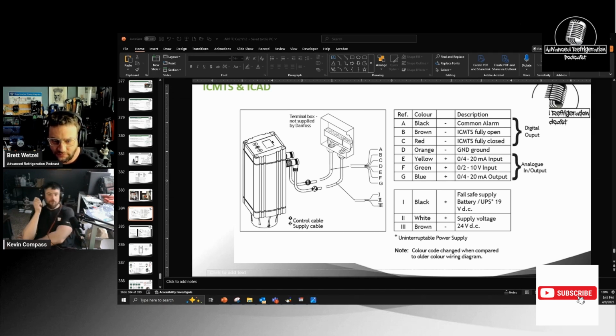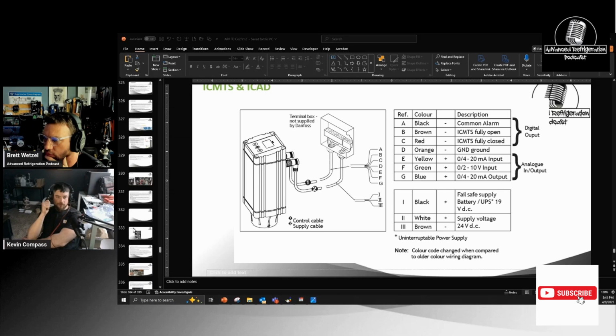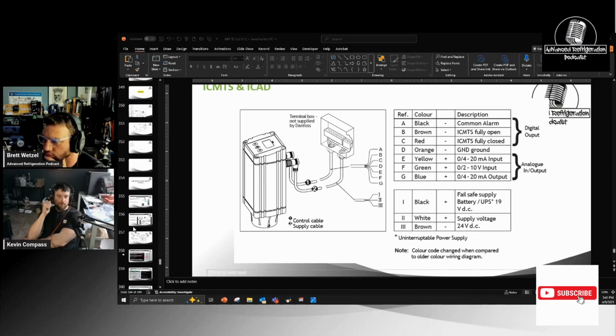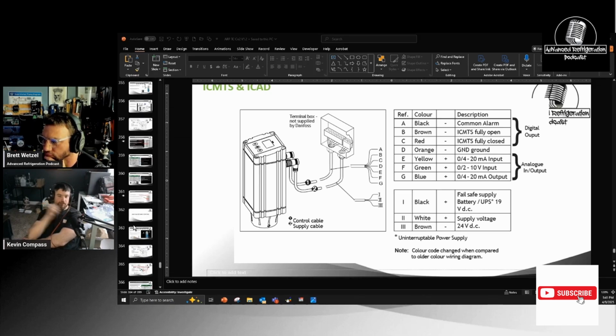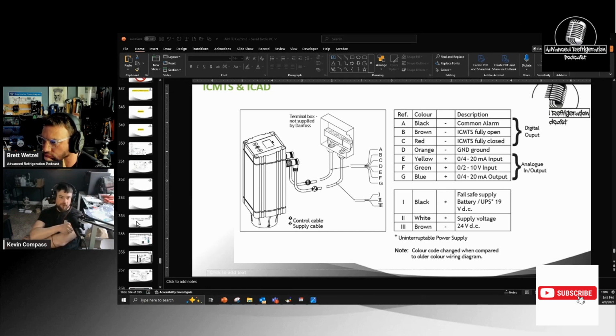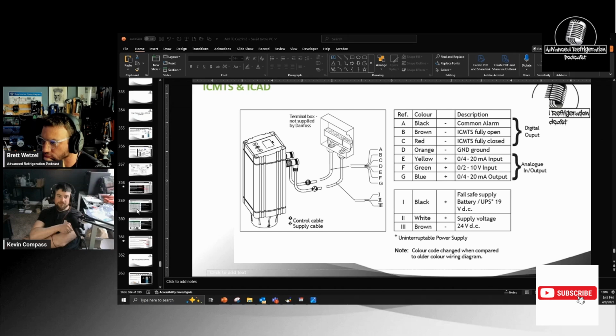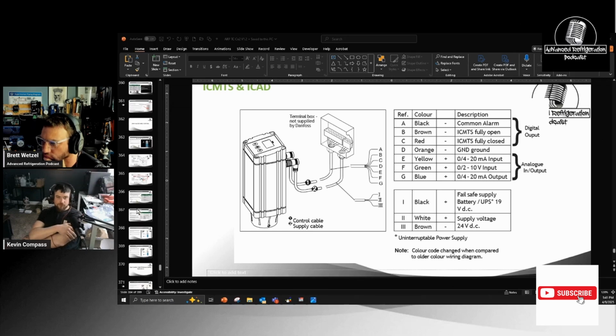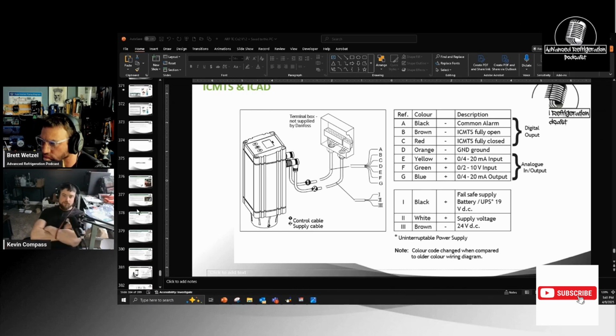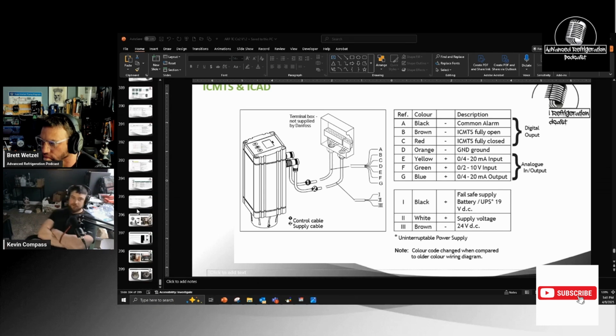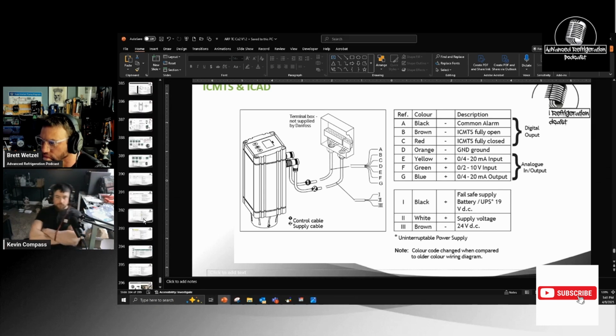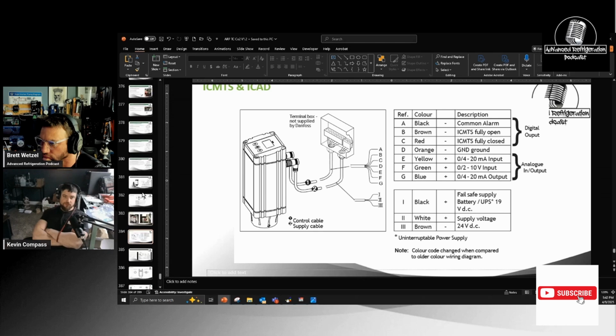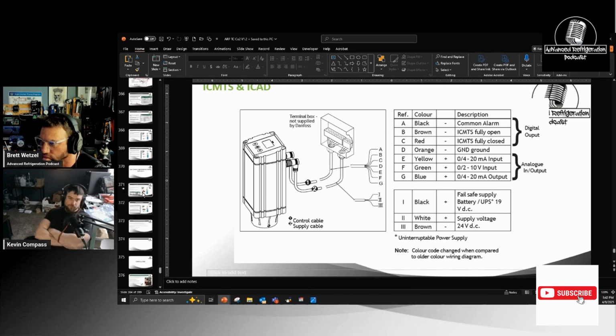So Danfoss also makes a ICMTS valve. This is a bipolar stepper motor, just like a ICAD valve would be. So it is a high pressure bipolar stepper motor. The ICM and the ICMTS are the two valves they have. The ICMTS comes with the built-in pressure transducer, a Danfoss built-in high pressure transducer. So if you were using a Danfoss valve driver, it just plugs right in, easy peasy. Now, an ICM valve is the same one, just a different body without the pressure transducer tap.